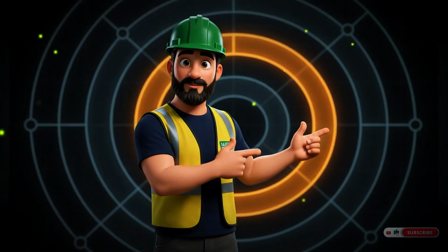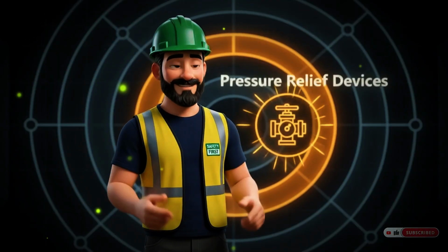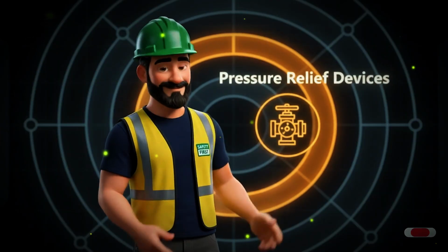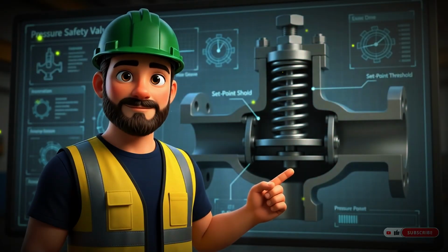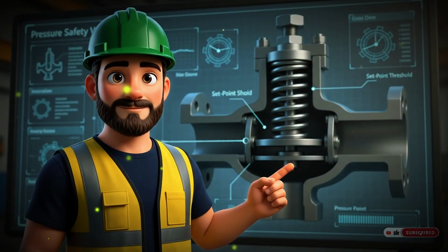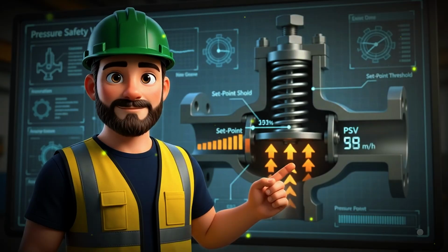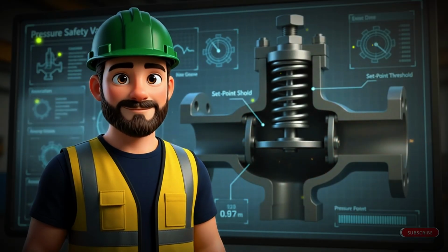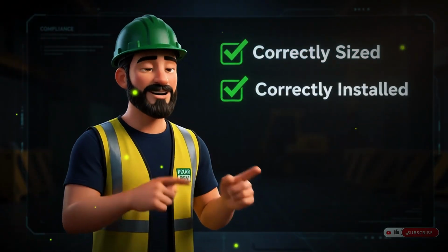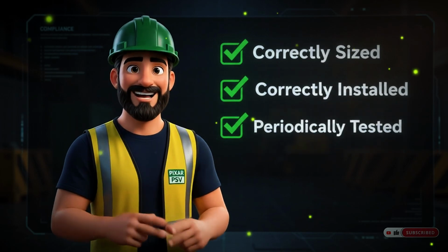The fourth layer is the pressure relief devices. PSV, pressure safety valves, are perhaps the most critical safety devices in the entire system. They are set to open automatically at a specific pressure, releasing excess pressure before the vessel reaches its structural limit. But simply having a PSV is not enough.